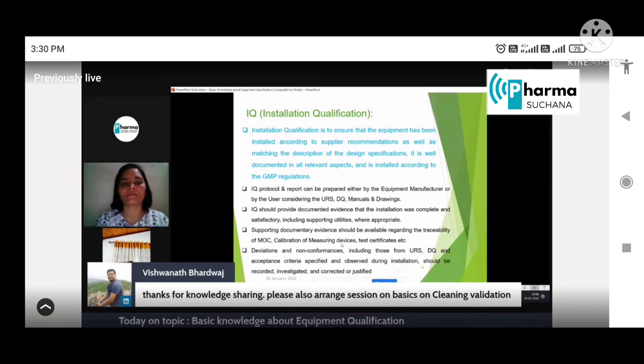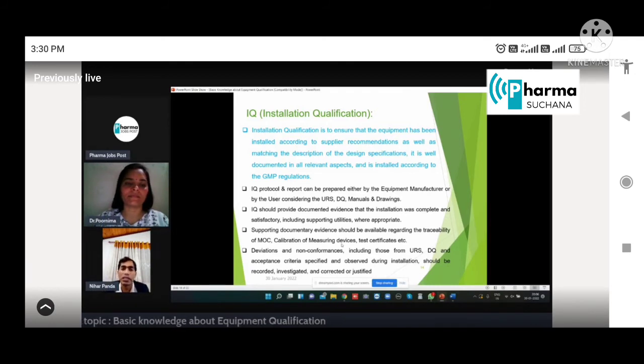Basically, IQ is the documented evidence. We have to keep documented evidence that the equipment is installed in its designated location as per the requirement, as per the feasibility, and as per the design, installed with all the utility facilities and with all the requirements of GMP and safety facilities and feasibilities. We have to ensure. How to ensure?